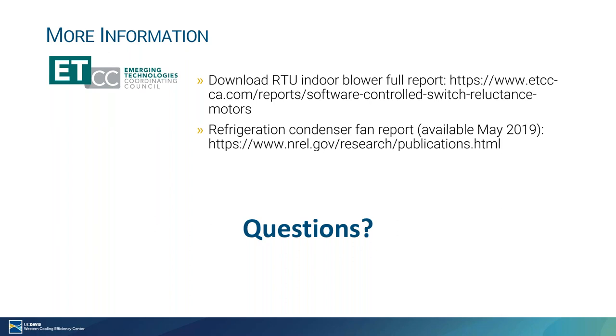In the laboratory testing, we did notice a difference in sound during the benchtop, but when it's in the RTU, the sound of air moving can dampen it out, and in the field testing, we had no complaints from the Walmart store about a change in noise. I think that's definitely an area for future research, to quantify the noise profile.